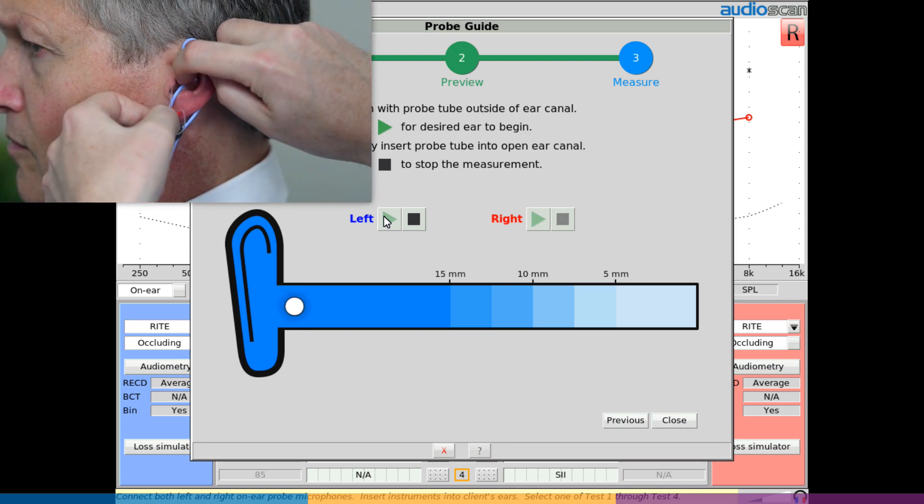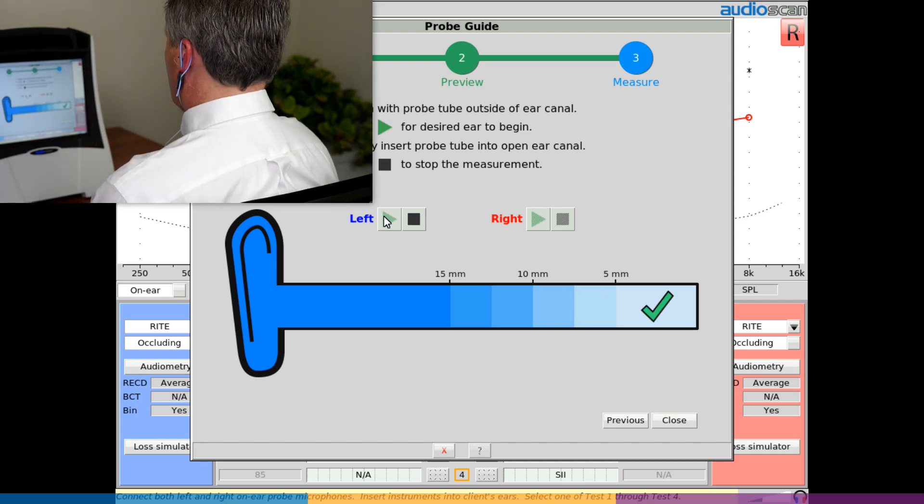For the desired ear, click the Play button to start. A broadband noise will be presented from the loudspeaker. Starting outside the ear canal, slowly insert the probe tube around the front of the lanyard. When the probe tube tip has reached an appropriate depth, a green check mark will be shown on-screen, accompanied by an audible chime. Click Stop to complete the procedure.